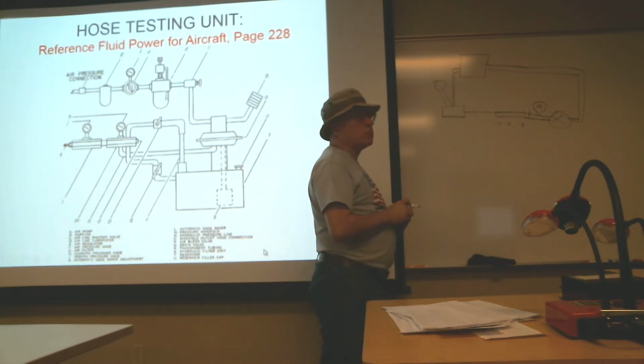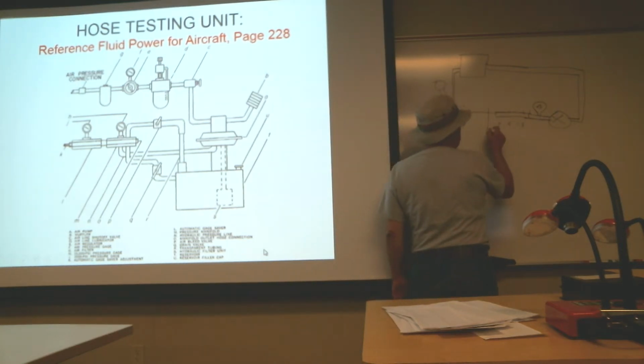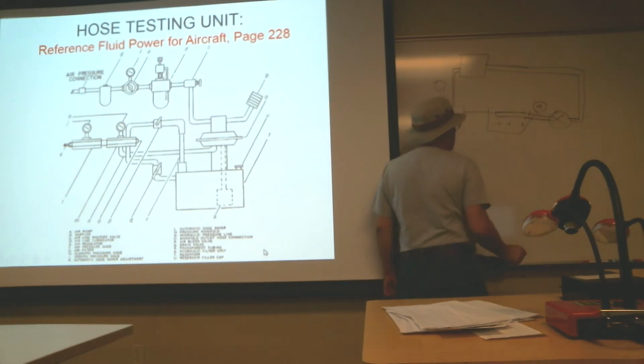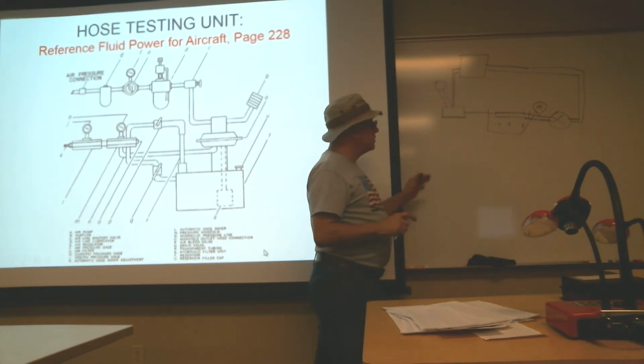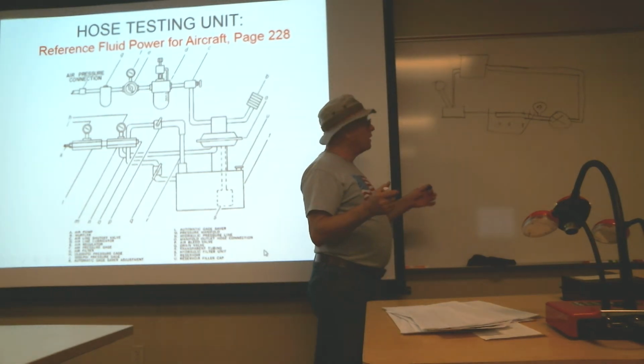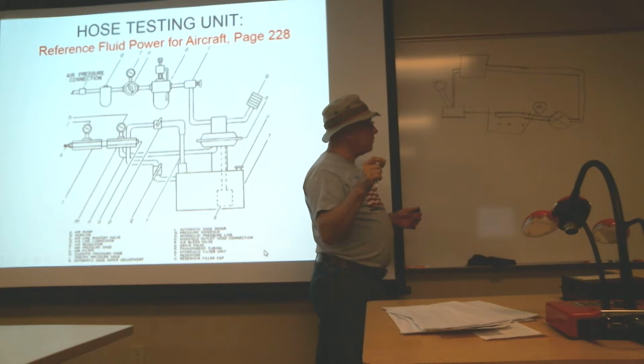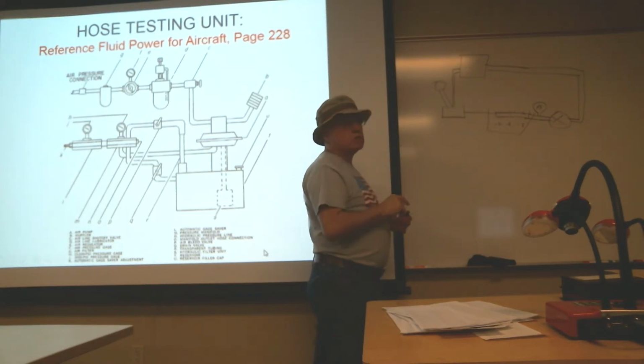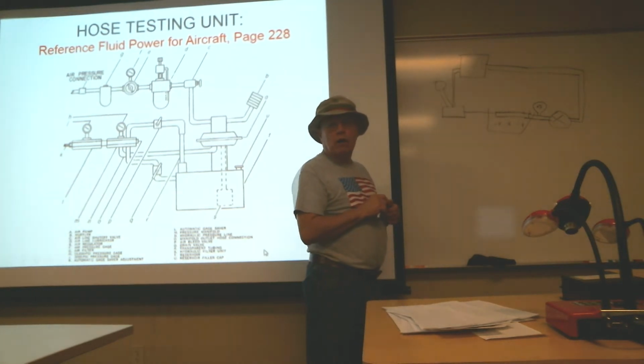So all you have to do is put the appropriate fitting on the hose and cap it at the end in order to be able to test pressure. To control leakage, a lot of them have a catch basin on the bottom. So what you do is you bleed the lines of air and then cap off the ends of the tubing or the hose. Then you close the shutoff valve and use the hand pump to develop static pressure in order to check the hose. And again, the standard is usually about 1.5 times system pressure for a minimum of how long?